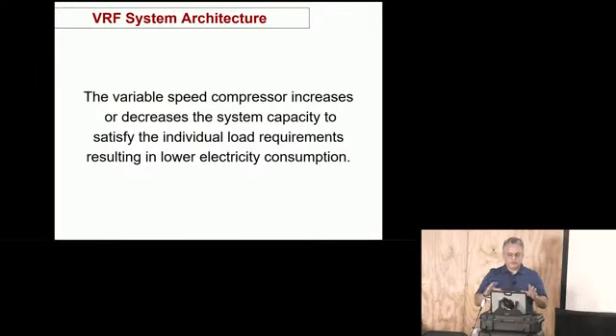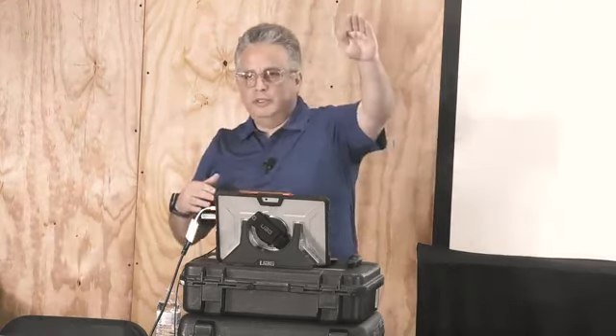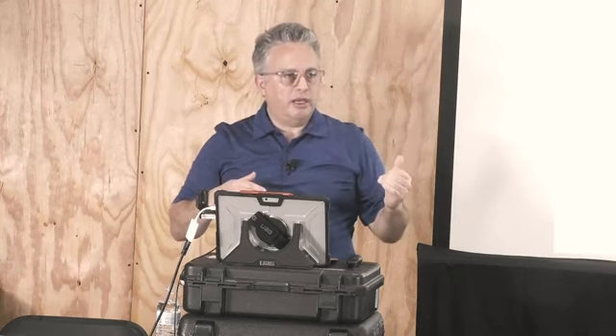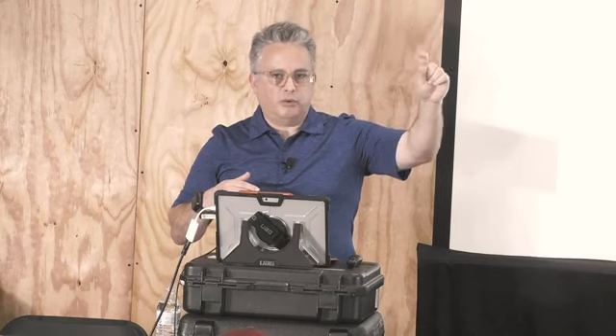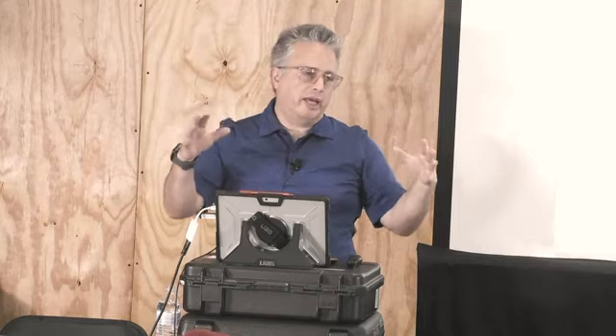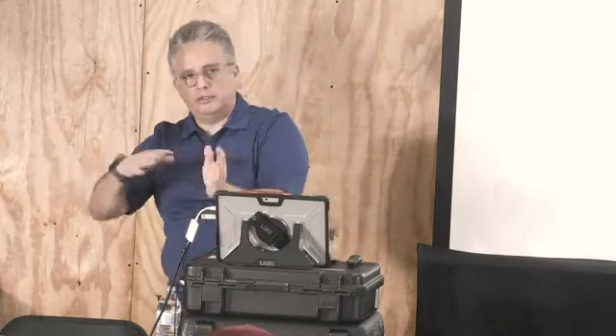The variable speed compressor increases or decreases the system capacity to satisfy the individual load requirements, resulting in lower electricity consumption. So if you have a high load in a space, the compressor is going to ramp up, deliver refrigerant to that indoor head. Indoor head will satisfy the space. As soon as the space is satisfied, then the compressor will ramp down. The refrigerant into that coil will be reduced, and thus all that energy can either be put into another indoor unit, or the compressor will just ramp down to off. And so that's how you can have full and part load efficiencies.